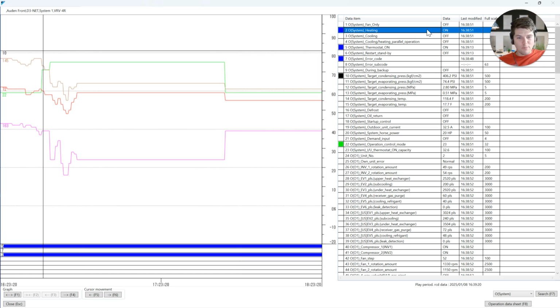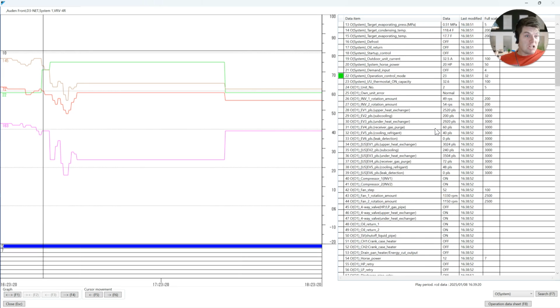That's why troubleshooting using operation control mode is levels above these stinking on-off controls that you see at the top. Now I know this entire window at the beginning is doing something different to get ready for what? Defrost. Okay. Now that we know it's getting ready for defrost, let's look at defrost.